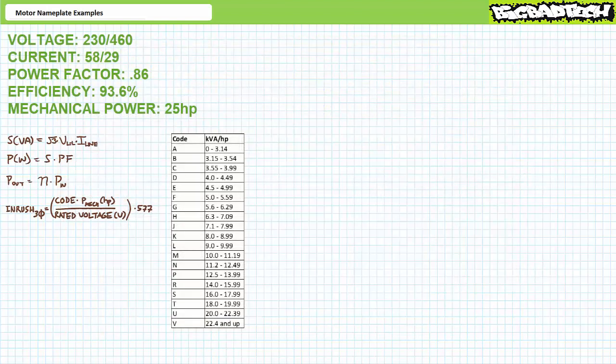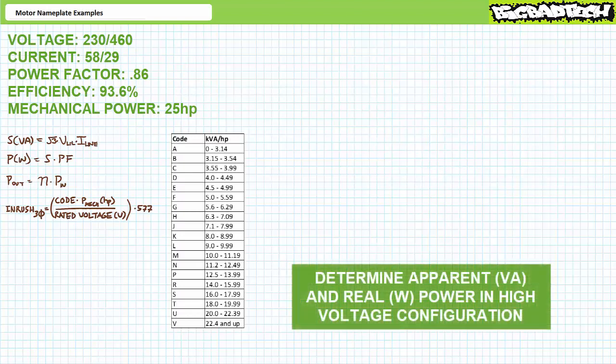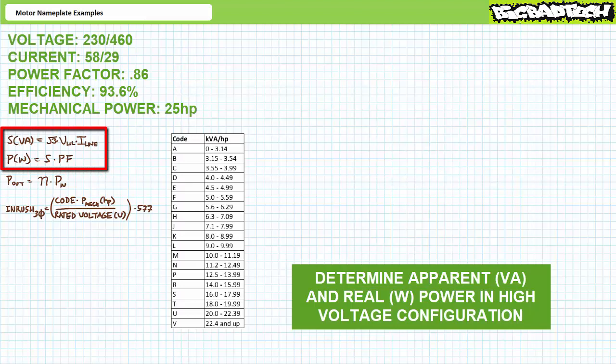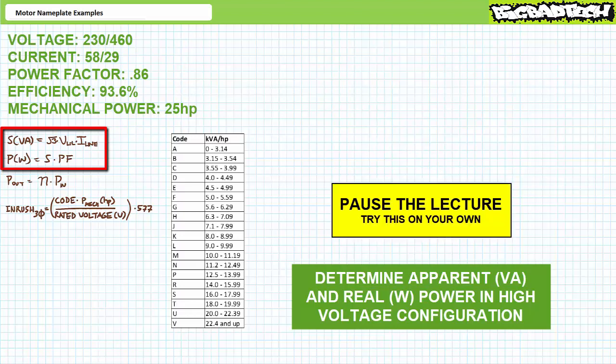While we've got the electrical data in front of us, let's perform some basic electrical calculations. First, see if you can determine the apparent power in volt amperes and real power input in watts drawn by this motor at the rated condition — for the high voltage configuration. Apparent power in a three-phase AC system equals √3 times line-to-line voltage times line current. Real power input equals apparent power times power factor. Pause the lecture and try this on your own.